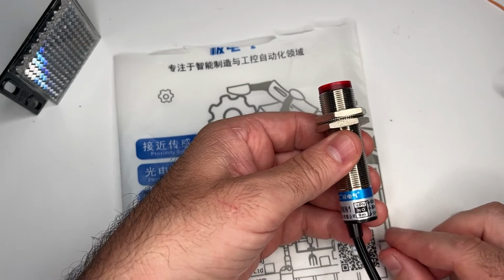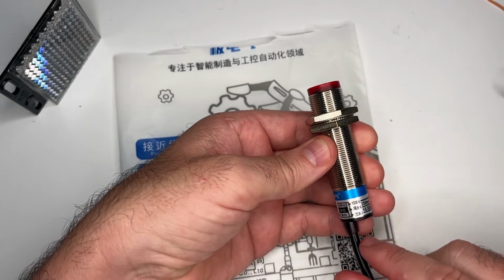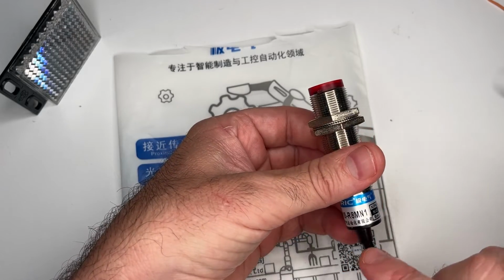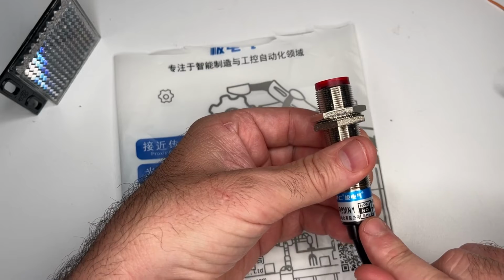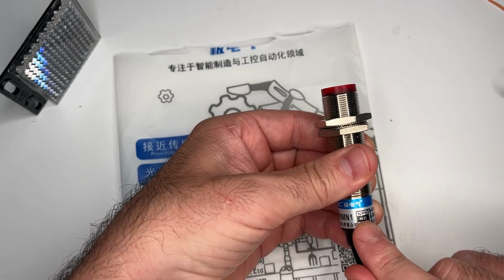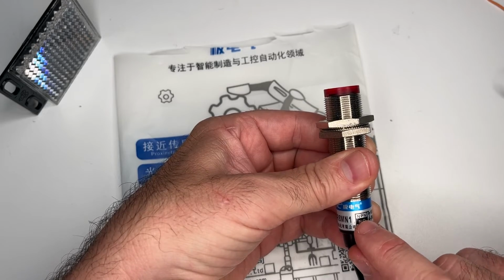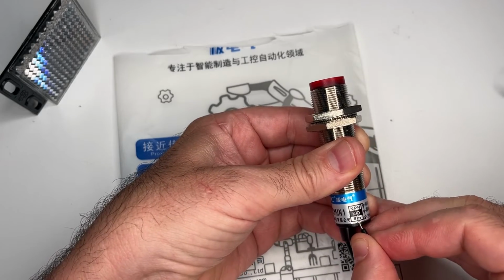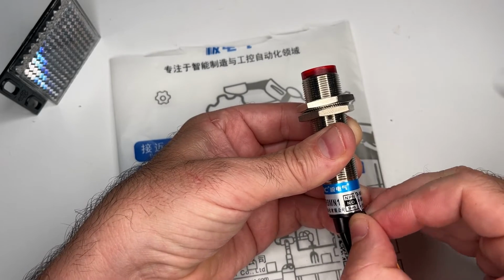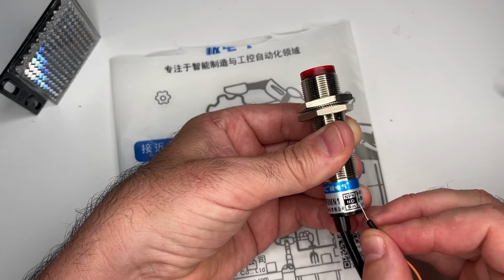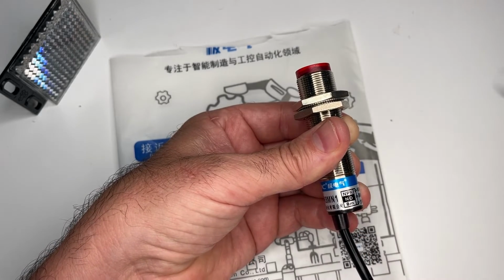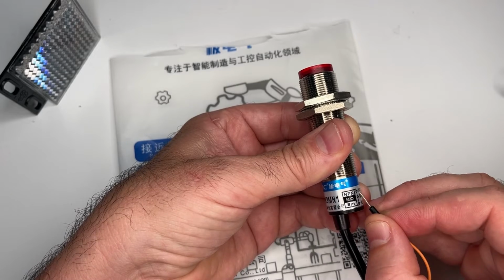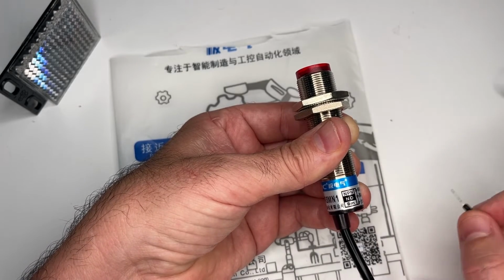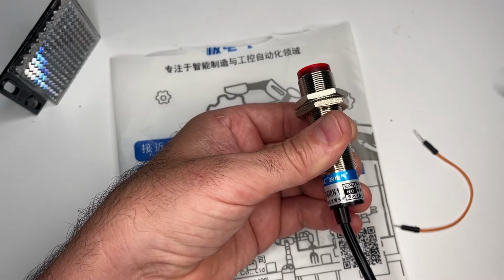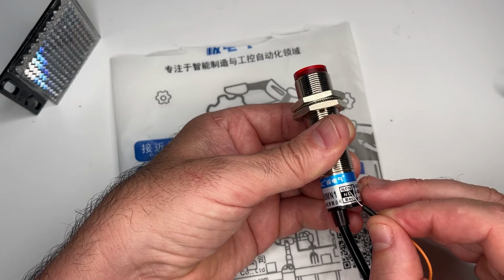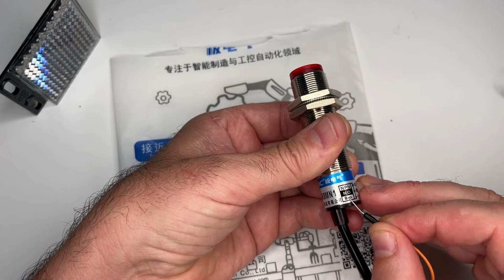Once you get into commercial grade sensors, there's a bit more technical stuff to keep in mind. They have an onboard transistor - this one is an NPN, meaning if you supply a positive voltage to the sensor, it will close a negative circuit. It's also NO, normally open. You can buy these in any combination - PNP or NPN, NO or NC (normally closed). I just happened to get this one, with an internal NPN transistor that's also normally open.